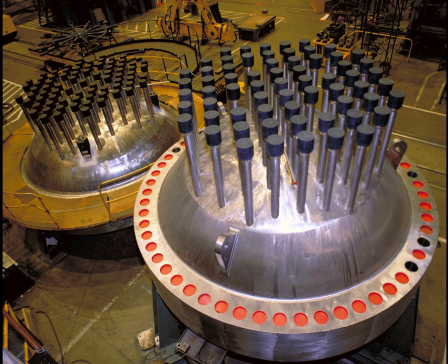The pressure in the primary coolant loop is typically 15 to 16 MPa, which is notably higher than in other nuclear reactors, and nearly twice that of a boiling water reactor. As an effect of this, only localized boiling occurs and steam will recondense promptly in the bulk fluid. By contrast, in a boiling water reactor the primary coolant is designed to boil.